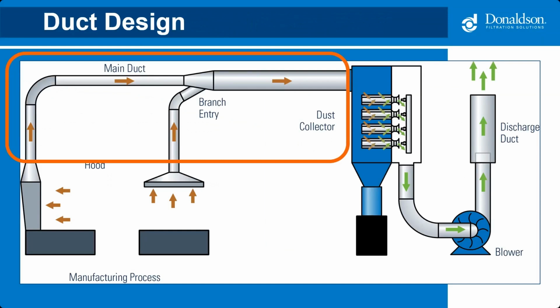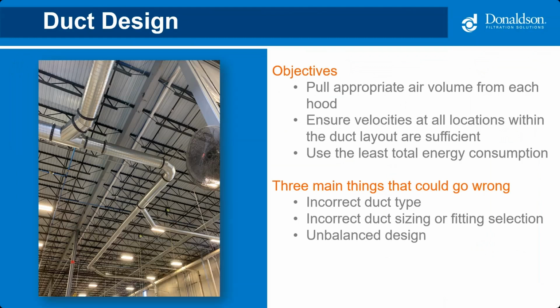Sure, thanks. Once we design the proper hood to capture the contaminant, the goal is to move the particulate to the filtration systems through a series of ducts. The properly designed duct system should, one, pull the minimum airflow required at each hood. Two, maintain velocities required to transport materials through the duct to the collector. And three, you should do this using the least amount of energy possible and minimizing any wear and tear on the duct components. A few common mistakes that I see are the wrong duct type, wrong size, and an unbalanced system.